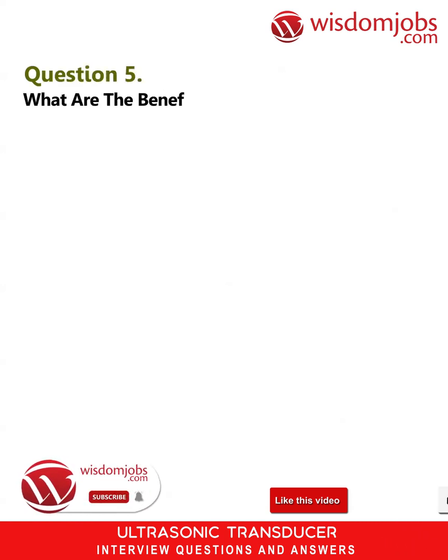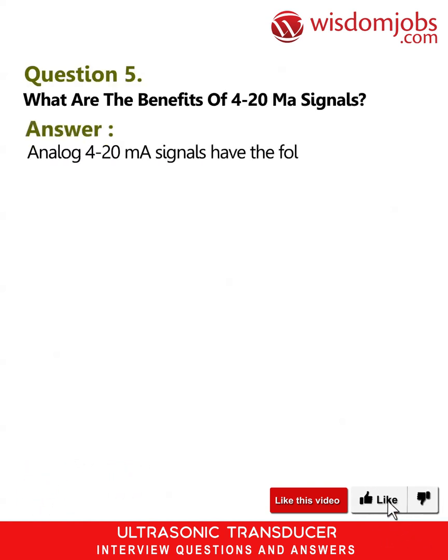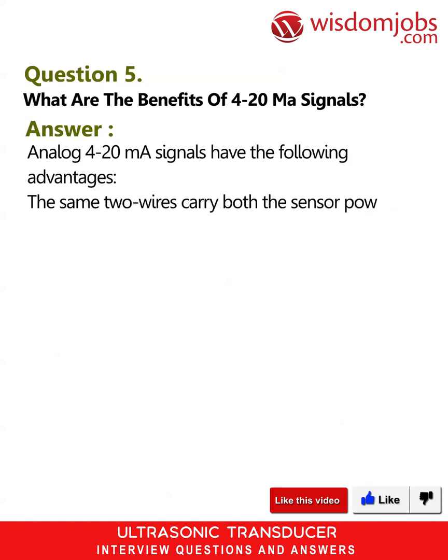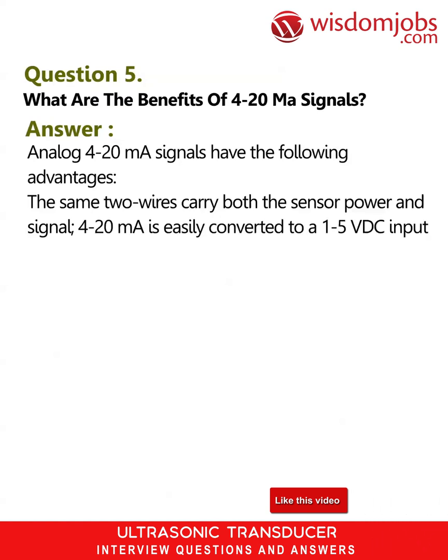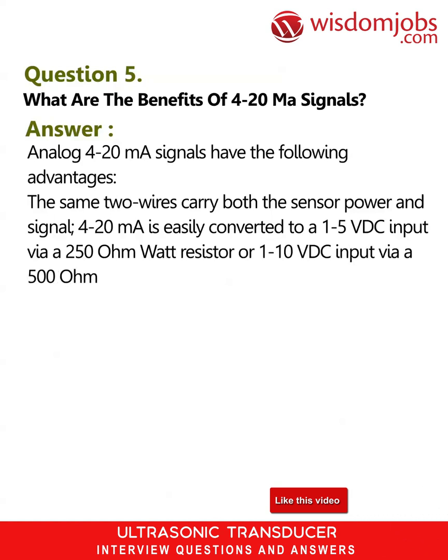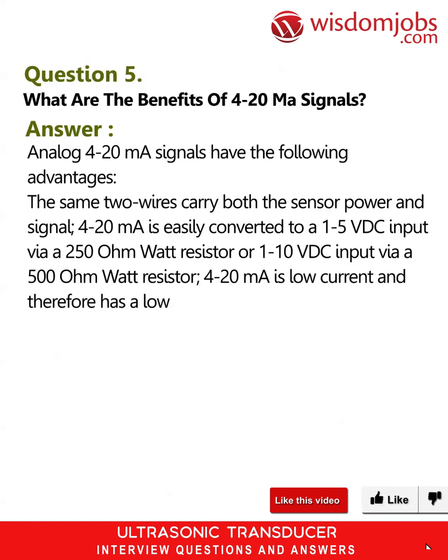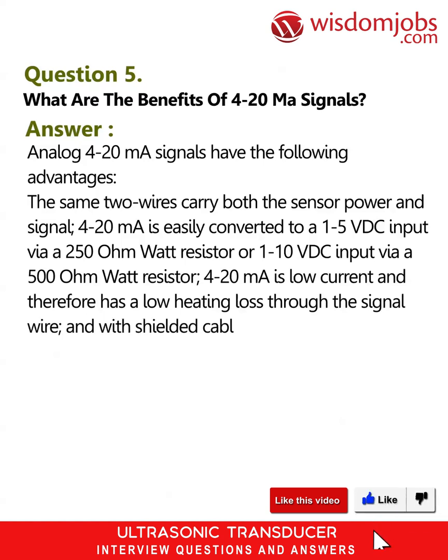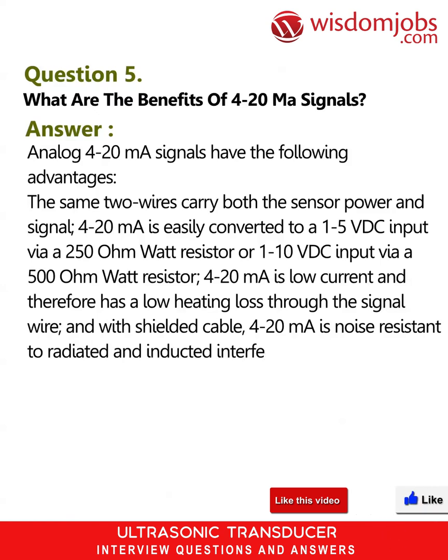Question 5. What are the benefits of 4 to 20 mA signals? Answer. Analog 4 to 20 mA signals have the following advantages. The same two wires carry both the sensor power and signal. 4 to 20 mA is easily converted to a 1 to 5 VDC input via a 250 ohm resistor or 1 to 10 VDC input via a 500 ohm resistor. 4 to 20 mA is low current and therefore has a low heating loss through the signal wire, and with shielded cable, 4 to 20 mA is noise resistant to radiated and induced interference.